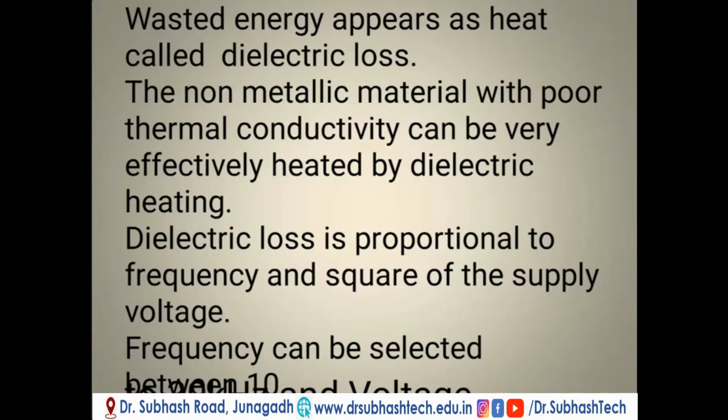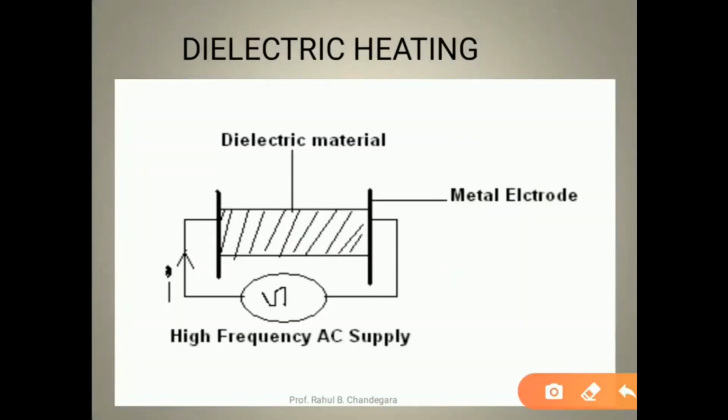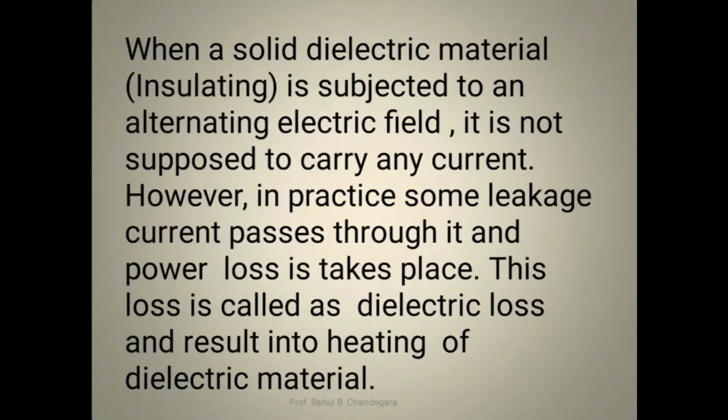Non-metallic material with poor thermal conductivity can be very effectively heated by dielectric heating. In that we put non-metallic material here, so that we can produce dielectric loss and heating. Dielectric loss is proportional to the frequency and the square of the supply voltage. Frequency can be selected between 10 to 30 megahertz, with very high voltage.